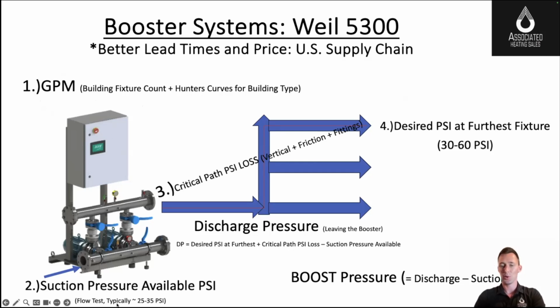Usually there's an 80-20 rule here with the boosters. So 80% of the time, these boosters live at 20% of their demand. Vice versa, 20% of the time, they might see 80% of their demand. So when we talk about redundancy and building some redundancy into this flow, our duplex systems, each pump could handle 80% of the flow. And that's how we do redundancy. And so you can definitely get by if one of these pumps is down.